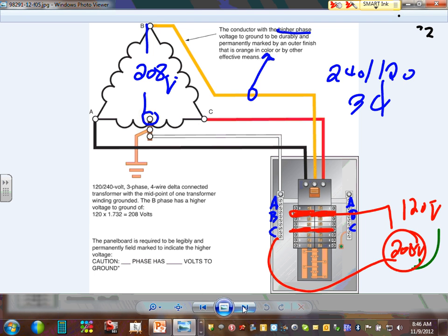So this is another system, not commonly used. This system you have to warn it. Phase B has 208 volt to ground. You have to have a label on it. So the electricians and apprentices, when they walk here, they say, hey, don't take anything from phase B into the neutral. You can't believe how many people burn a lot of equipment, guys, from this system. You hear the stories all the time. The electrician walked in here. Oops, here's a slot for a 20 amp circuit. Plug it in and feed your lights, and bam, bam, bam, bam, burn all your lights. Can I have thumbs up? We understand this special system.